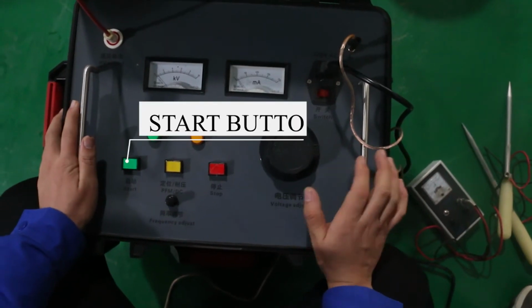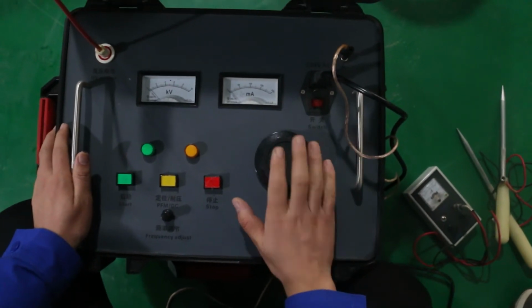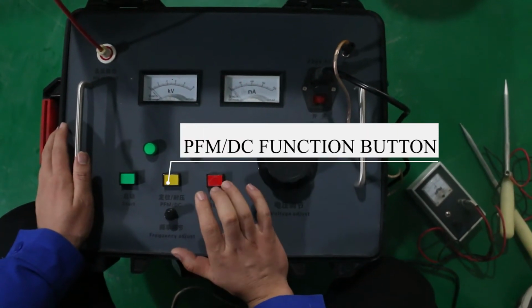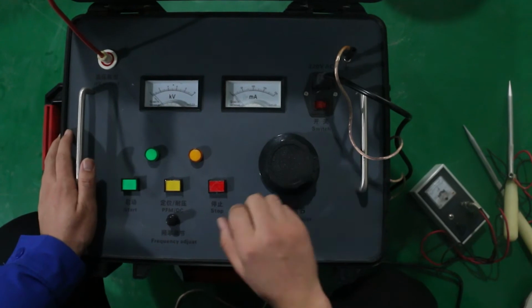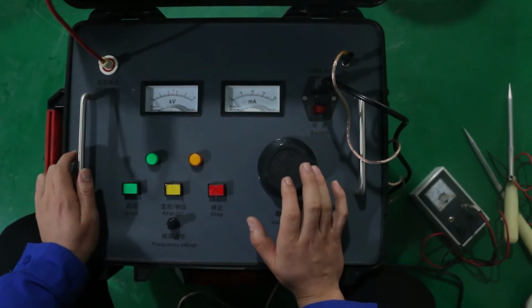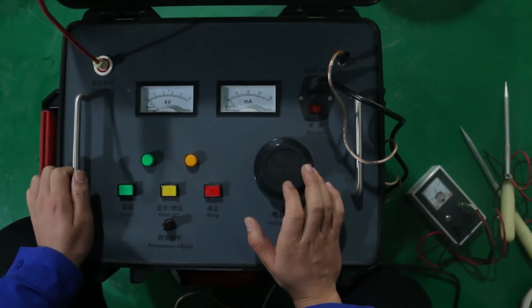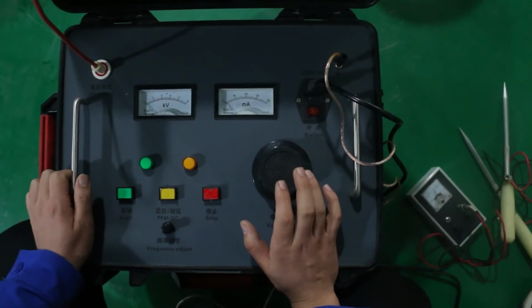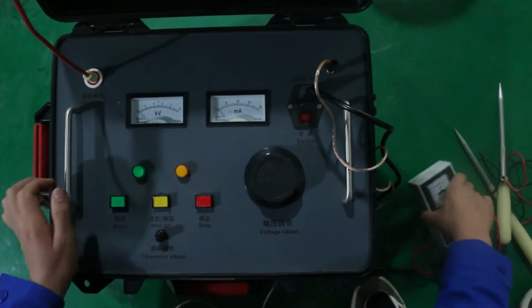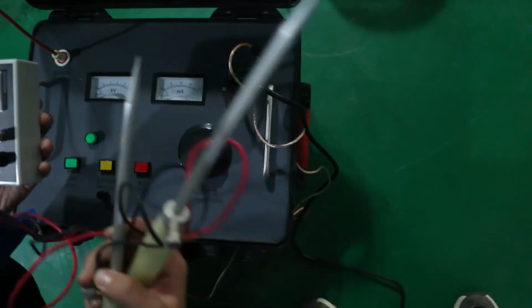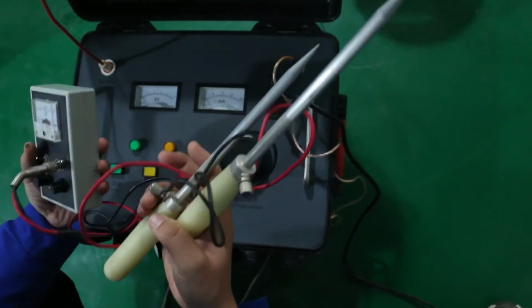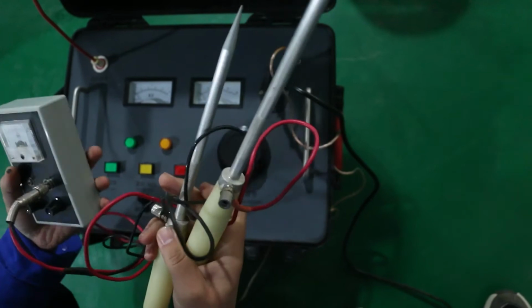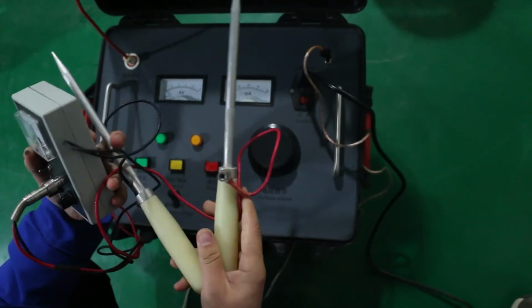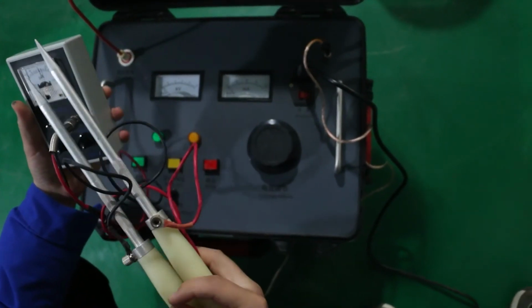The green key is the start button. The yellow one is the PFM/DC function button. Yellow light on is for pressure test. Yellow light off is for positioning test. When doing the outer sheath location test, just switch to positioning test. The withstand voltage function can be used during the withstand voltage test for the cable sheath. The voltage can be raised to 10 kilovolts, and the current can be up to 200 mA.